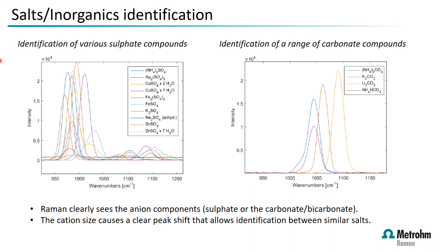The system can also identify inorganic materials. With Raman we can analyze larger salts such as sulfates, carbonates, phosphates, and nitrates, as well as more complex materials such as minerals and gemstones. We see a clear peak shape associated with the sulfate peaks, and the different cations bound to that sulfate cause a defined peak shift — allowing us to specifically identify ammonium sulfate, potassium sulfate, sodium sulfate, and so on. This is extremely useful because on infrared techniques these samples look very similar and would need alternative verification.